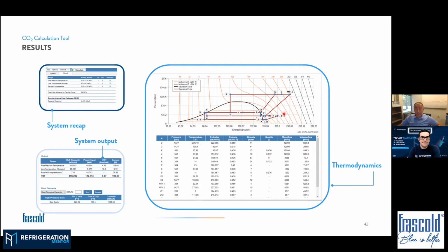What's cool, since we've been discussing discharge temperature, is that the P-h diagram gives us two different colors at the temperature that's usually allowed without any cooling - typically we say 284 Fahrenheit. As long as you stay below that, you don't need any cooling, but as soon as you cross that temperature level, the software gives you an alarm. And when you go into the black side of the isothermal curves, it tells you the temperature is too high, so something's wrong with the selection.